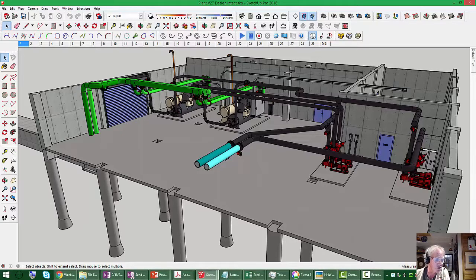The plant certainly looks like it's set up to leverage that, and that's an energy conserving thing, right? If you vary the flow, remember that equation, the flow's in the numerator. If you reduce the flow, you'll reduce the energy requirement, partly because you reduce the flow, but also because the pressure drop in the piping is a function of the square of the flow. And so there's actually a cubic relationship, for a fixed condition, between the flow in a system and the power required to produce that flow. So it's a very powerful relationship.